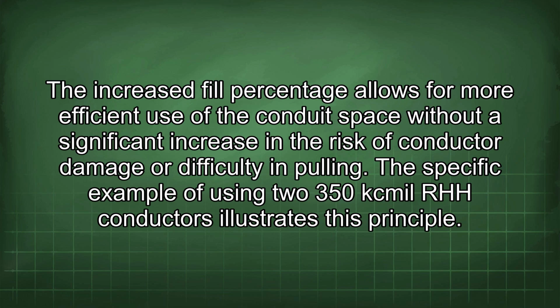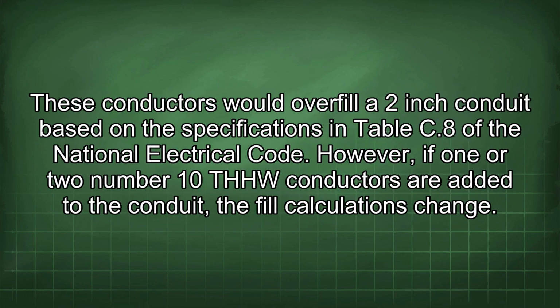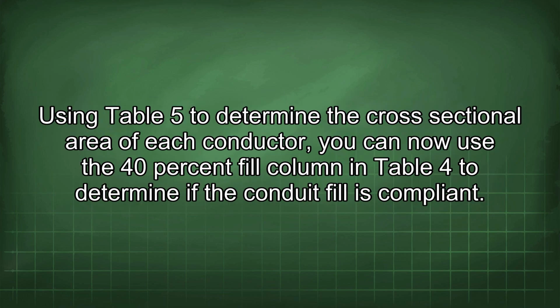The specific example of using 2 350 kcmil RHH conductors illustrates this principle. These conductors would overfill a 2-inch conduit based on the specifications in Table C8 of the National Electrical Code. However, if 1 or 2 number 10 THHW conductors are added to the conduit, the fill calculations change. Using Table 5 to determine the cross-sectional area of each conductor, you can now use the 40% fill column in Table 4 to determine if the conduit fill is compliant.